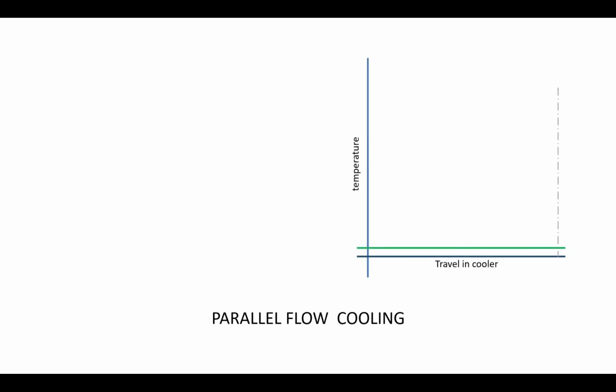Parallel flow cooling example. Fresh water inlet temperature is 51.5 degrees Celsius, while seawater inlet temperature is 32 degrees Celsius. Fresh water and seawater will flow in the same direction. Seawater temperature will increase while fresh water temperature will decrease. Seawater temperature is 34, fresh water temperature 50.